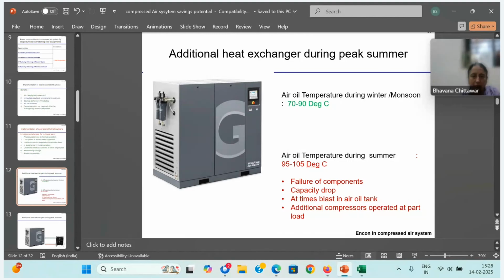So to avoid that, some clients don't operate compressors at full load. They switch on other compressors so that this compressor loads and unloads. Any compressor has to be rated to run at full load always. Compressor efficiency is high and specific power consumption low when compressors are operated at continuous load only, not load-unload. I don't prefer that. But due to this temperature rise, you are compelled to run another compressor to avoid the failure. So I questioned him, your capacity requirement is lower than the full compressor, why are you operating a second compressor?